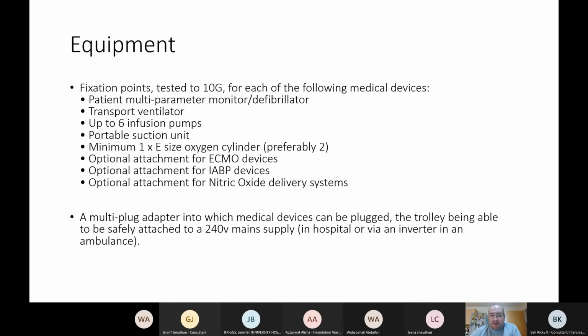The equipment, as I said, is put below the patient, and the reason for that is to reduce the centre of gravity. It also reduces the chance of equipment coming loose and flying around the ambulance, and all of the things that you may need. So that's monitor, ventilator, plenty of infusion pumps, suction, and other specialist attachments need to be fixed in a fixation that is also tested to 10 G. So we shouldn't be bolting on extra bits and pieces, because that can become dangerous if the ambulance moves suddenly.